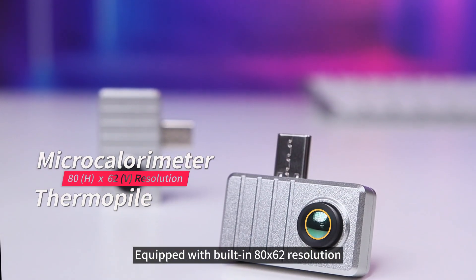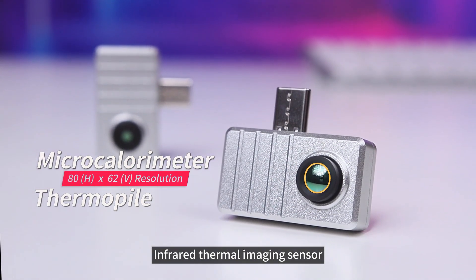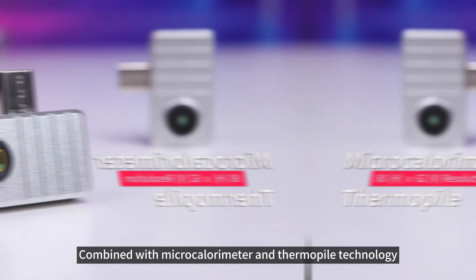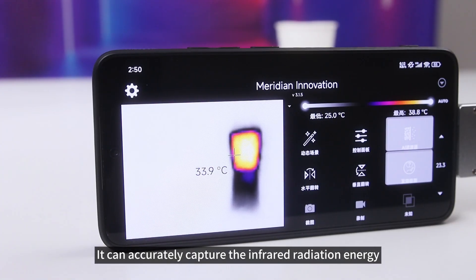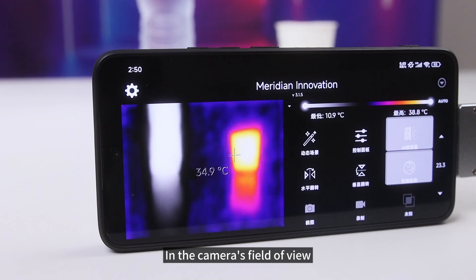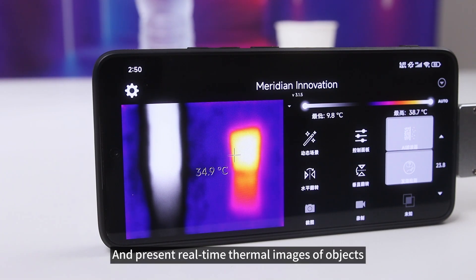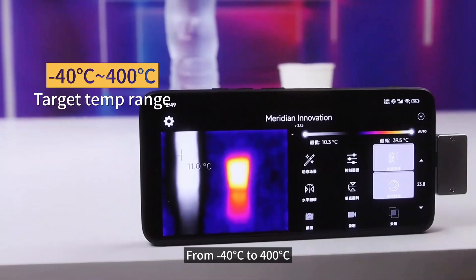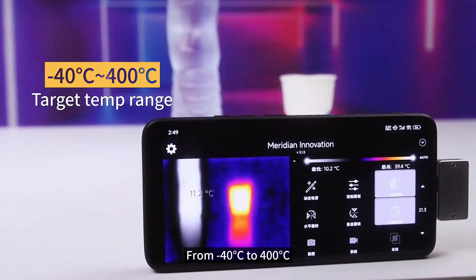Equipped with a built-in 80x62 resolution infrared thermal imaging sensor, combined with microcalorimeter and thermopile technology, it can accurately capture the infrared radiation energy in the camera's field of view and present real-time thermal images of objects. The temperature measurement range covers from minus 40 degrees Celsius to 400 degrees Celsius.